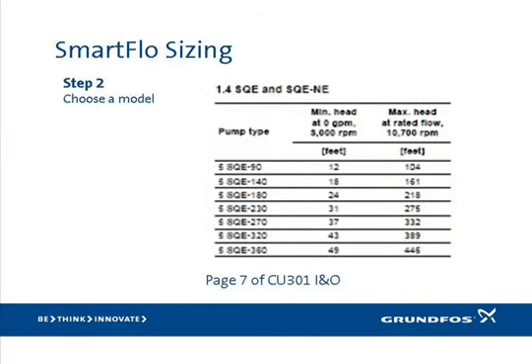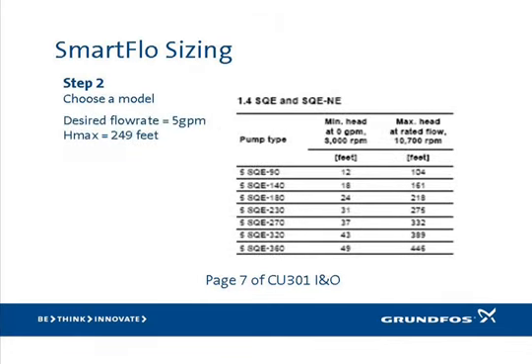For step two, refer to the sizing chart on page 7 of the I&O and choose a model based on the desired flow rate and the calculated head from step one. In our example, the customer needs only 5 gallons per minute and the calculated head is 249 feet. Choose from the chart a model from the 5 SQE family of pumps with a max head rating greater than our calculated max head of 249 feet. Based on that criteria, the 5 SQE 230 would be the best choice for our example application.